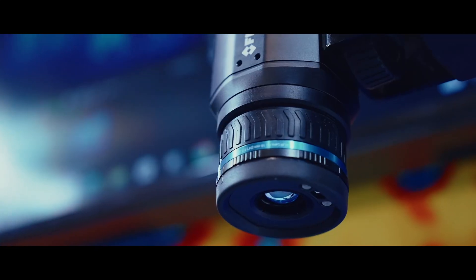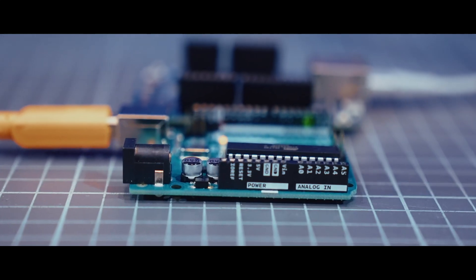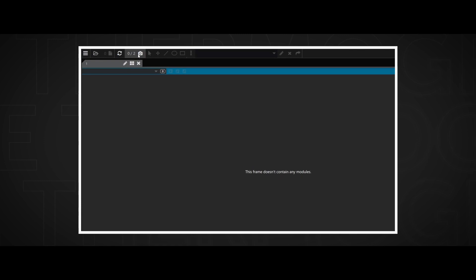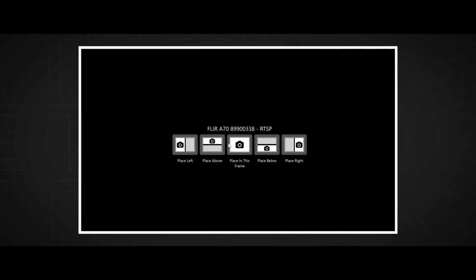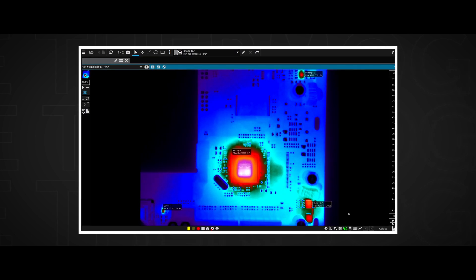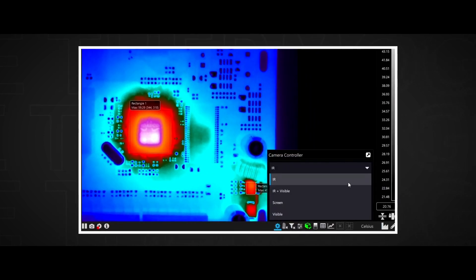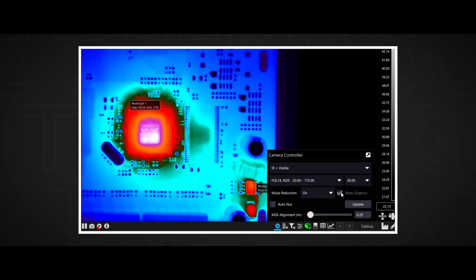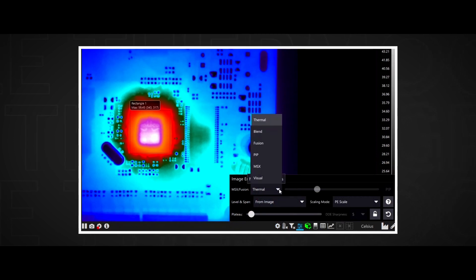Behind me we have a FLIR A70 camera looking at a basic printed circuit board. We're running FLIR Research Studio, and connecting to the camera is very simple. I go into the connection section of the software and click connect to RTSP stream. Initially we're just looking at the infrared imagery on the screen, but when I go into the camera controller, I can switch to IR and visible. At that point, the FLIR MSX and fusion options can be viewed under image enhancement. The degree to which the images are fused can be edited in this interface also.